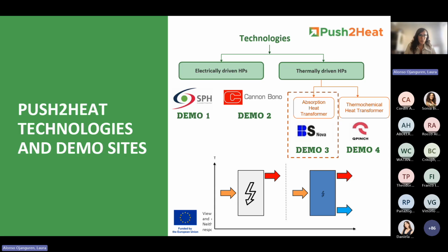And normally this technology has 2 different temperature levels. So we have the waste heat input at a medium temperature level, and thanks to an electricity consumption in the compressor, we have the useful heat or the upgraded heat at a higher temperature level.